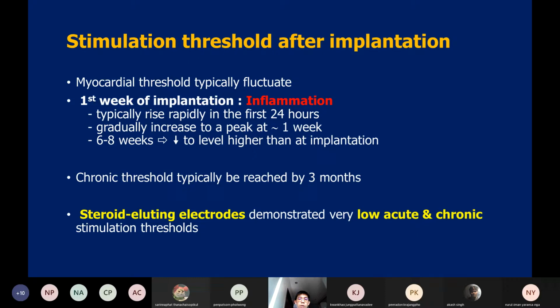So this is the chronic threshold where we program for the long term of the patients. After we implant patients with a pacemaker, we usually program the pacing threshold high, like 3 volts or 4 volts before, and after 3 months we usually lower the programmed threshold to the chronic threshold of the pacemaker. As I said before, this also happens with steroid eluting electrodes, but steroid eluting electrodes usually demonstrate a very low acute threshold, maybe similar to the chronic stimulation threshold, and this would save you energy consumption.